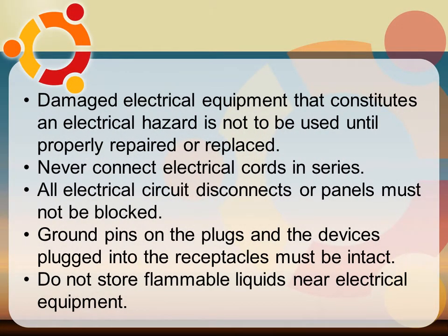Damaged electrical equipment that constitutes an electrical hazard is not to be used until properly repaired or replaced. Never connect electrical cords in series. All electrical circuit disconnects or panels must not be blocked. Ground pins on the plugs and the devices plugged into the receptacles must be intact. Then do not store flammable liquids near electrical equipment.